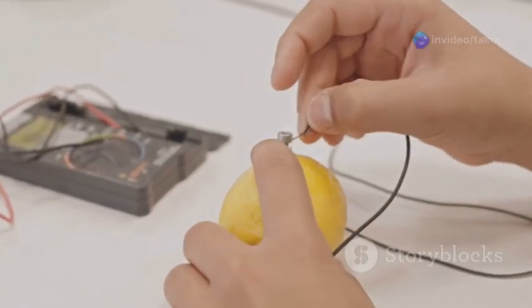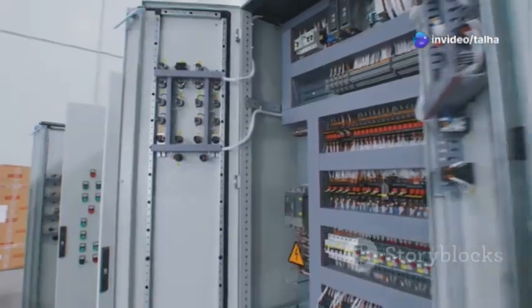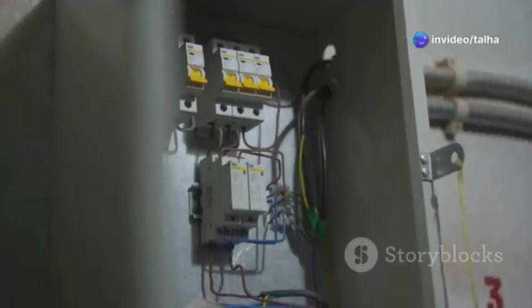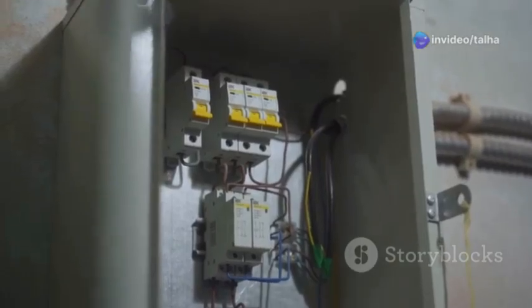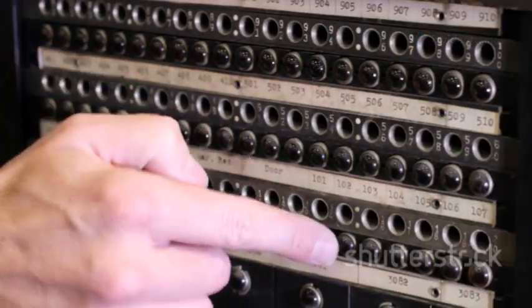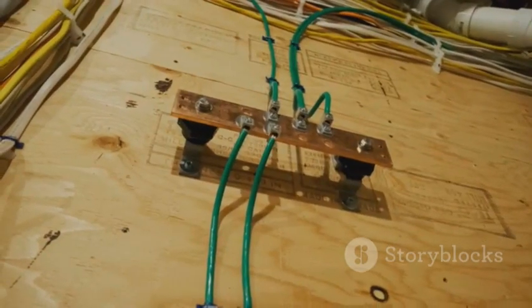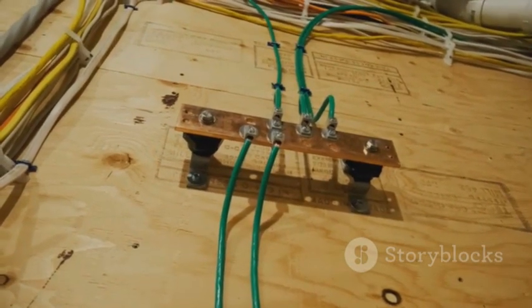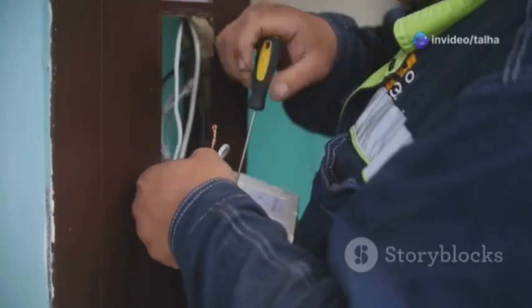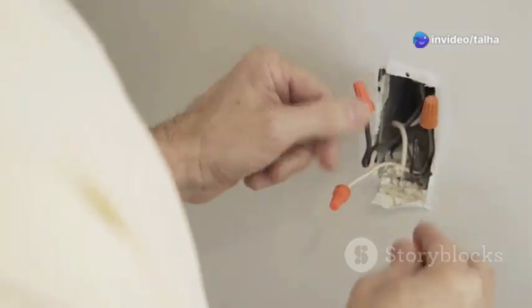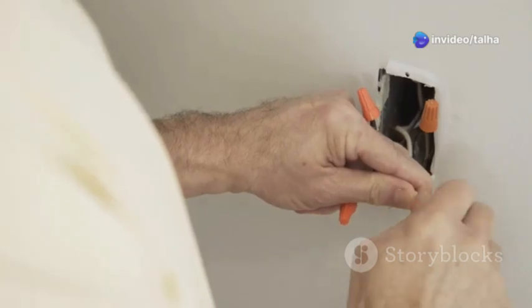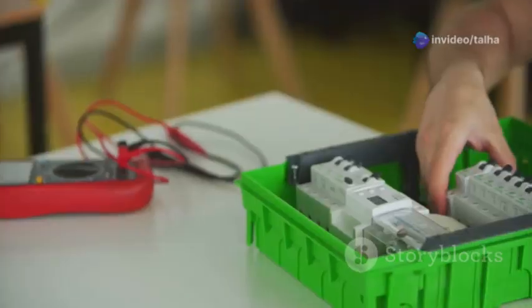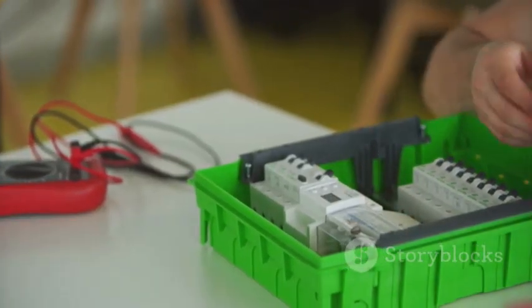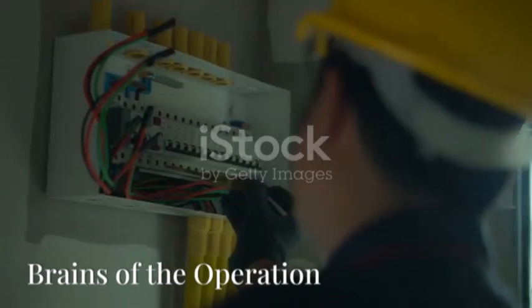Okay, let's get started. First, the power circuit. This is the strong part of our setup. 1. Connect the circuit breaker to the main power. This is where the electricity comes from. 2. From the circuit breaker, connect the wire to the contactor's input. 3. Connect the contactor's output to your motor. 4. Connect the motor's other wire back to the power supply. This completes the circuit. Remember, tight connections are important. Loose wires are dangerous.